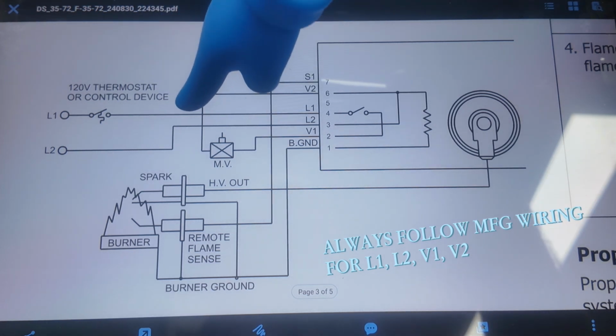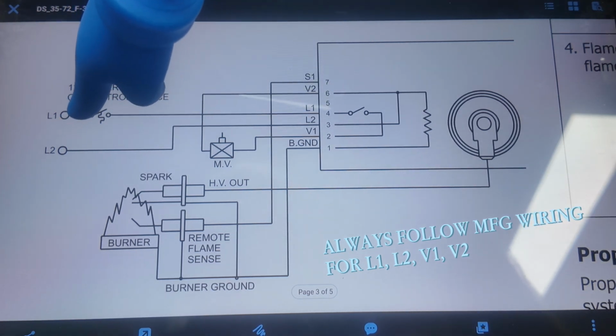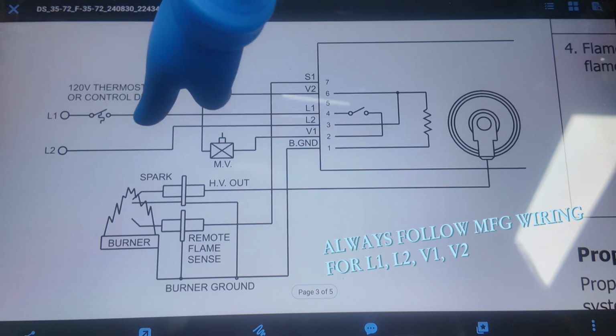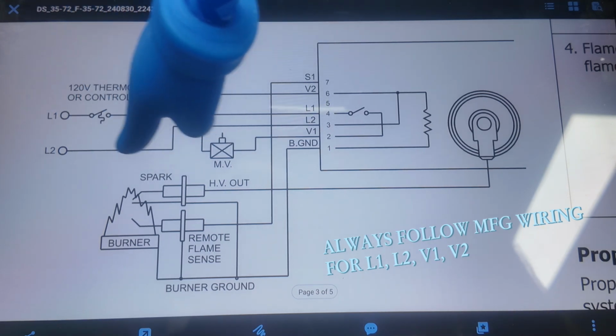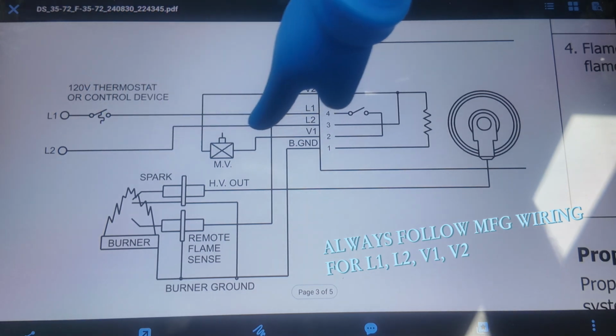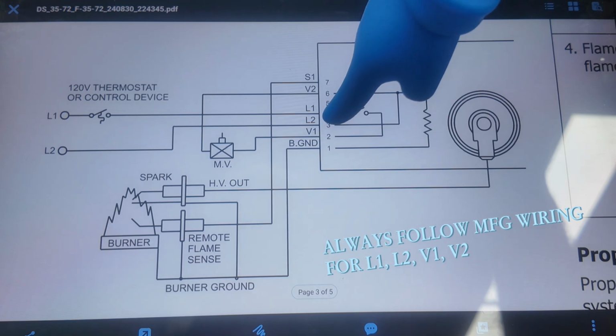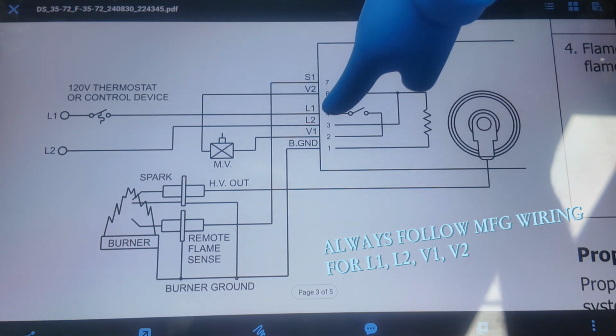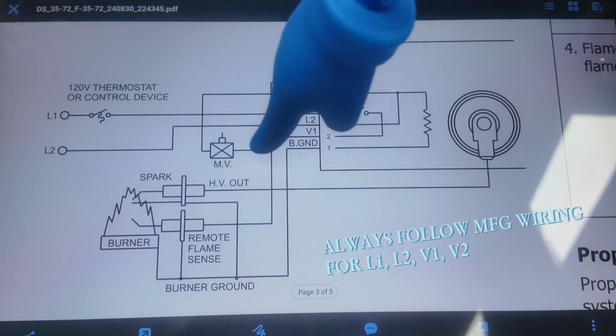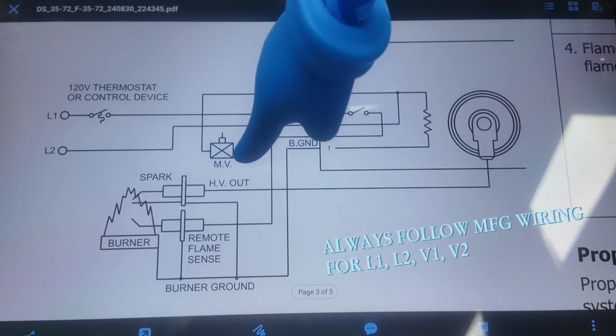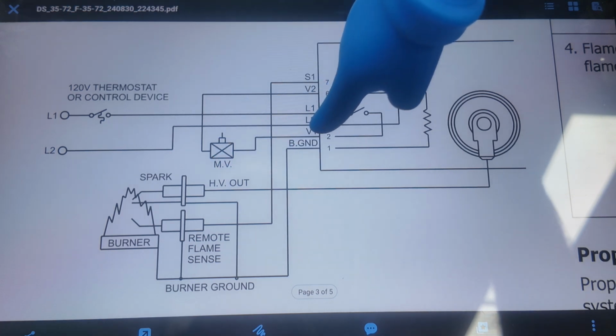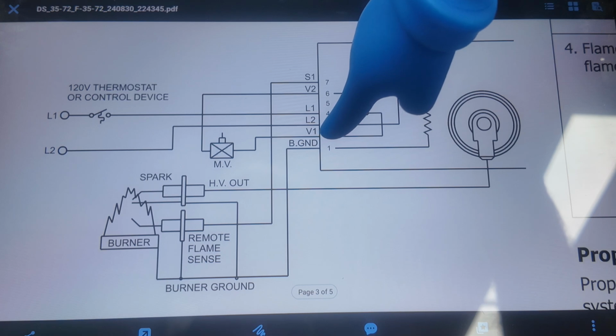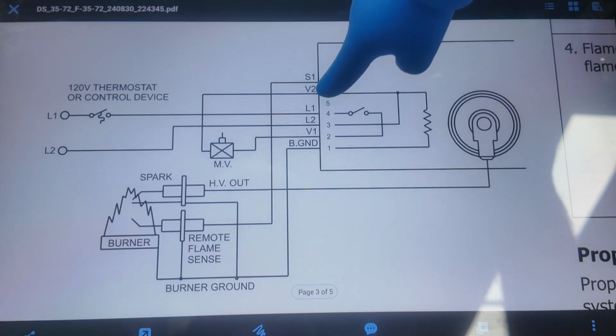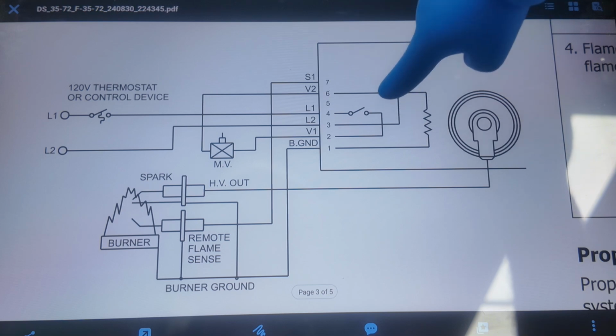So when we look here, we need 120 volt on this wire. We need neutral here. So neutral connects to L2. 120 volt connects to L1. Then we have the main valve, your gas valve. The one side of that connects to V1 and the other side connects to V2. This is all simple wiring. Most people don't get this goofed up.